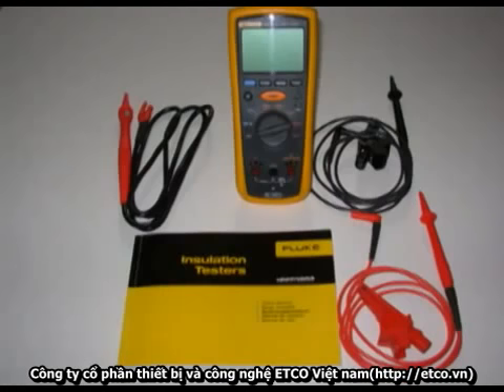Basically, you're applying a voltage, specifically a highly regulated, stabilized DC voltage, across a dielectric. And you're measuring the amount of current flowing through that dielectric, and then calculating, using Ohm's law, a resistance measurement. What we're really talking about here is leakage current. The resistance measurement is in megohms, and you use this resistance measurement to evaluate insulation integrity.